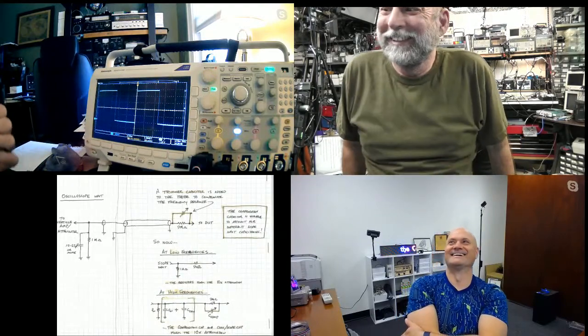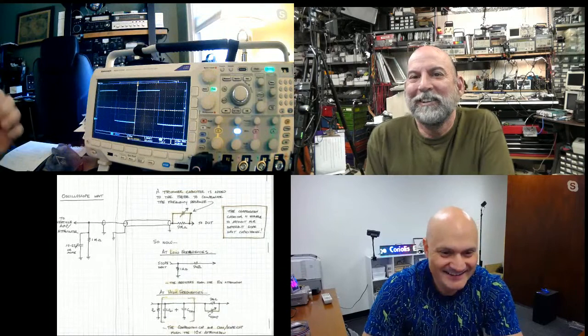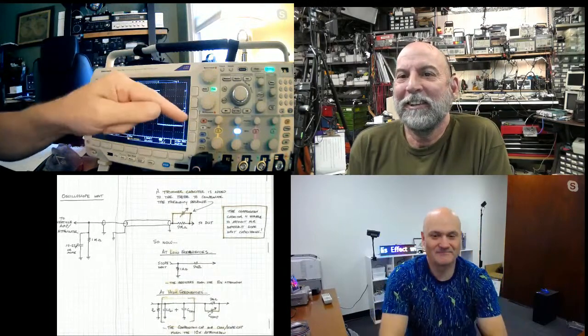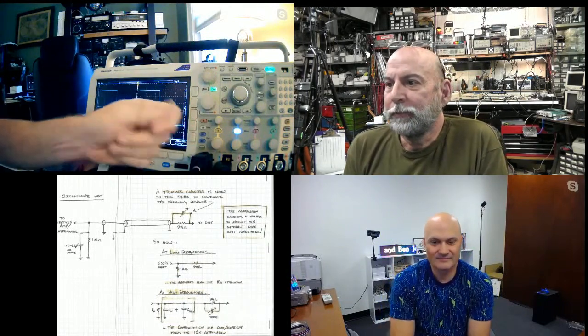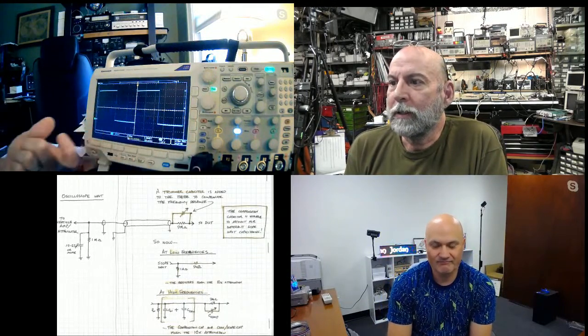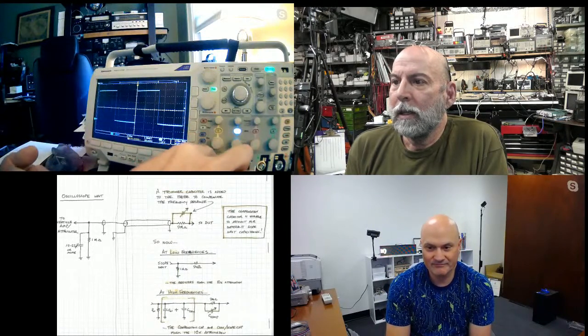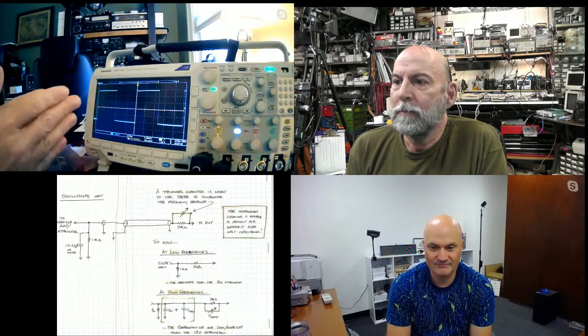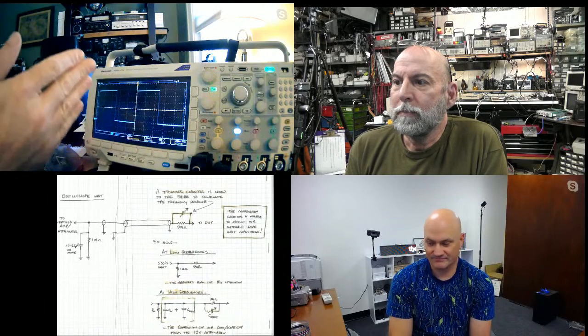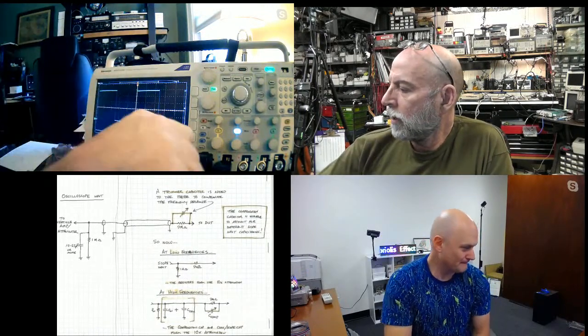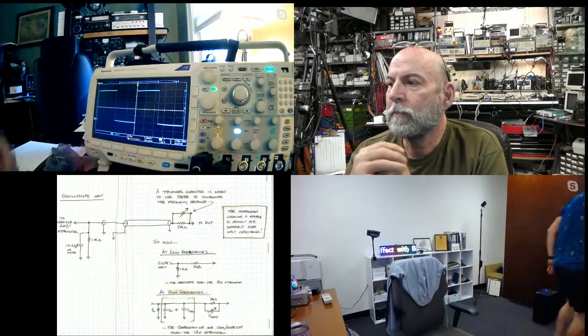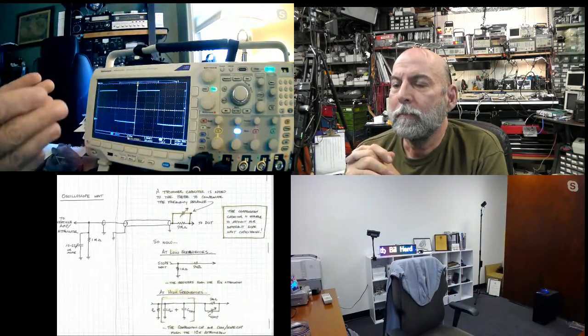Okay, right? Because it really comes down to the range of capacitance that the compensation adjustment can account for, which is limited. So a particular probe's compensation adjustment might only be able to compensate for 10 to 18 picofarads. And if your scope input capacitance is 22 picofarads, you won't be able to properly compensate it. And vice versa, it might be skewed the other way.